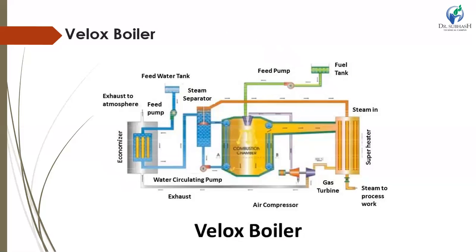This boiler works on the principle that whenever gas velocity exceeds the sound velocity, heat is transferred from the gas at a much higher rate than the rate achieved with subsonic flow. This fact is used in the Velox boiler to achieve a large amount of heat transfer from a given surface area.